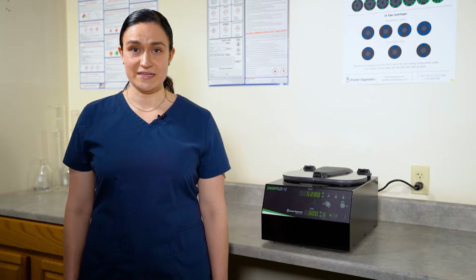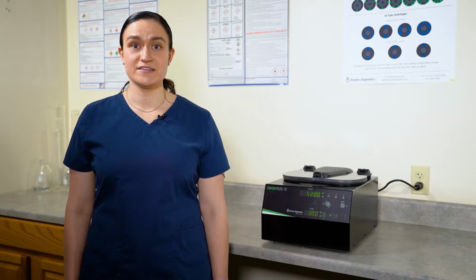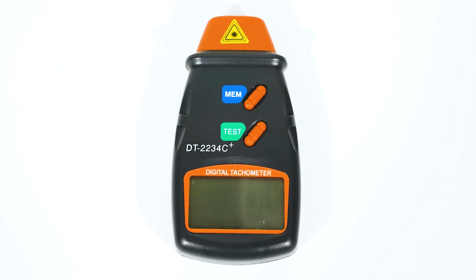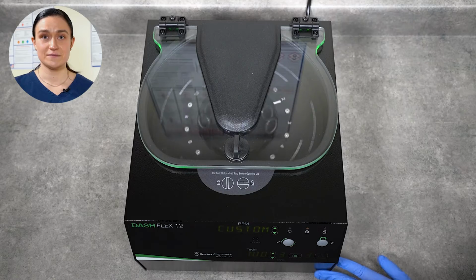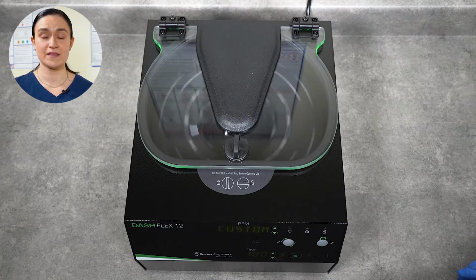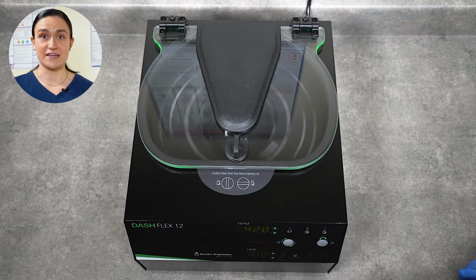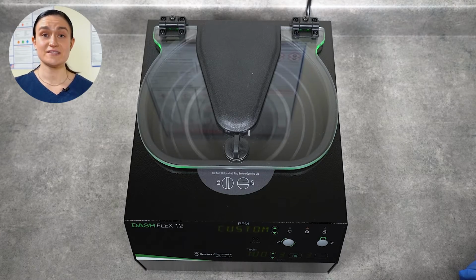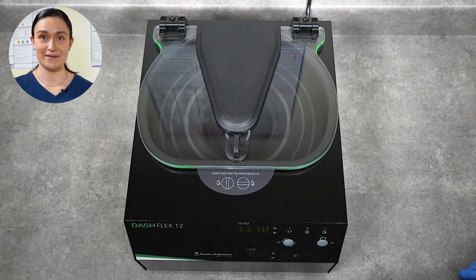Your Flex 12 requires no regular maintenance, but you may wish to verify the centrifuge spin speed. To verify the spin speed, you'll need a phototachometer, like the one shown here. Your lab should have a validated phototachometer for you to use for this purpose. Next, with your centrifuge plugged in and turned on, start it running on whatever cycle you would like to test. Give it a minute in order for that centrifuge to reach its full speed. You'll know it's at full speed when that timer begins counting down.